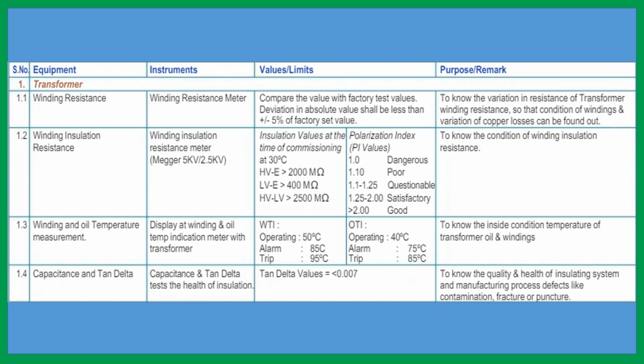But for the IR value, the insulation resistance, you have to maintain the minimum value. If it is higher, no problem, or if it is equal to this value also, but you cannot go below it. Okay. So I have given the values here. For winding resistance, they have told to compare the value with the factory test values. Deviation of plus or minus 5% is allowed. The manufacturer will give the test report, and from there you check the value, and plus or minus 5% variation is allowed.